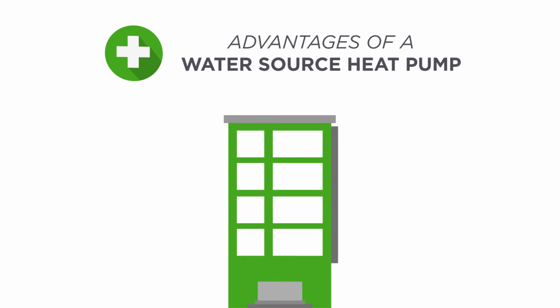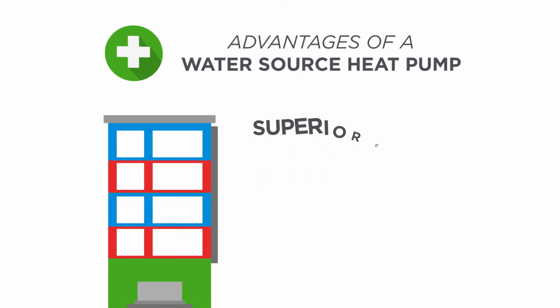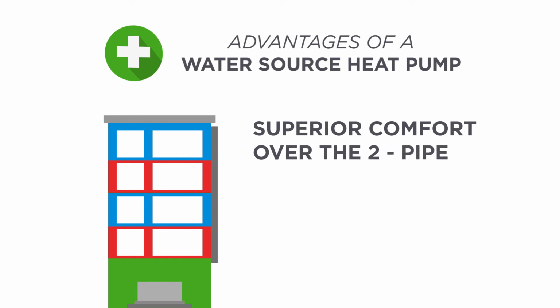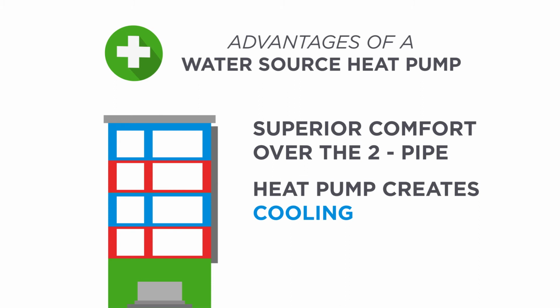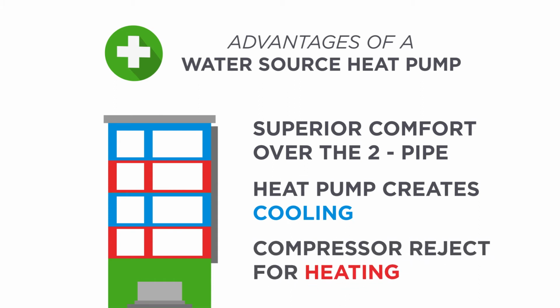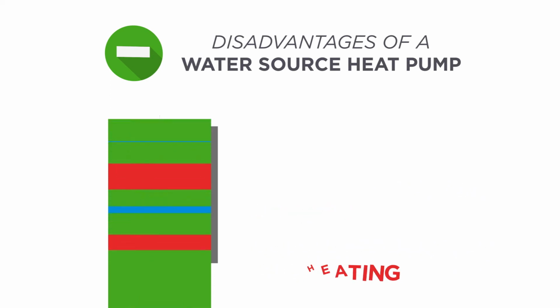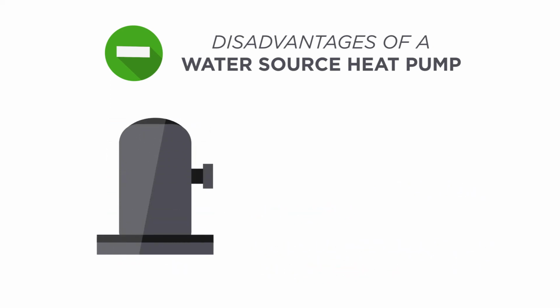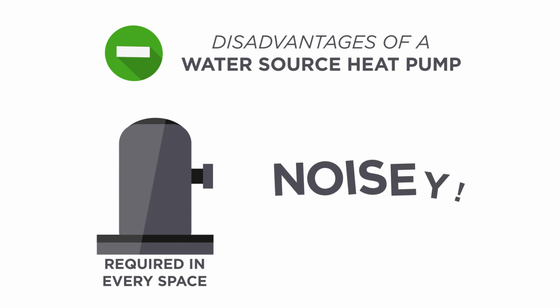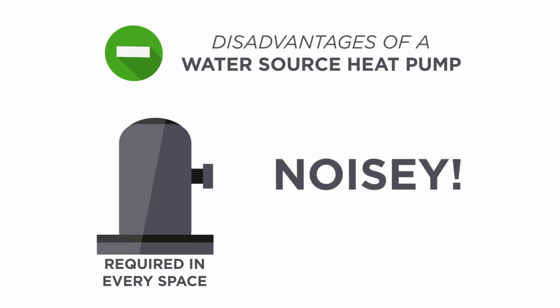But because different spaces can call for both heating and cooling simultaneously, it offers superior comfort over the 2-pipe. No chiller is required now because the heat pump can create cooling and utilize the compressor reject heat for heating. The disadvantage to using a water source heat pump system? The compressor or heat pump, which would be required in every space, is noisy. It's like having a mechanical room in the space itself.